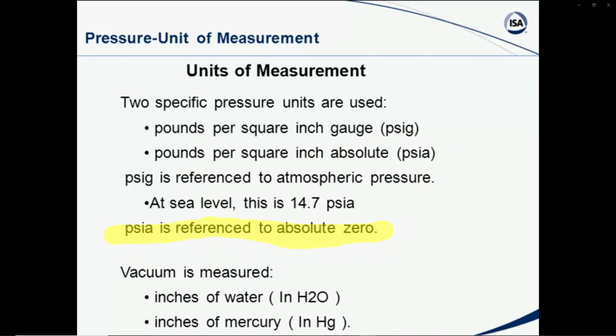So we need to understand these units. We need to know about PSI, pounds per square inch gauge, pounds per square inch absolute, and the fact that we also use inches of water and inches of mercury to display vacuum. A little side note that I sometimes ask people: if you're watching the weather on the news at night and they say that the barometric pressure is 30 inches, what are they saying? Many people don't understand what they're saying there. It's 30 inches of mercury. 1 inch of mercury is approximately 0.49 psi. So 30 inches of mercury is, surprise, 14.7 psia. So again, we're talking about absolute, we're talking about atmospheric pressure.